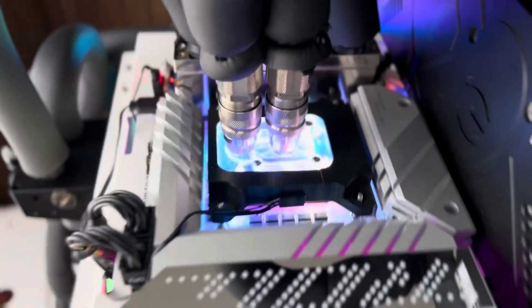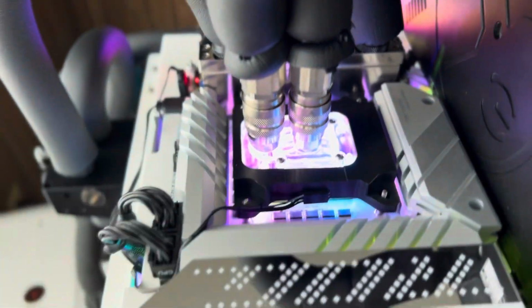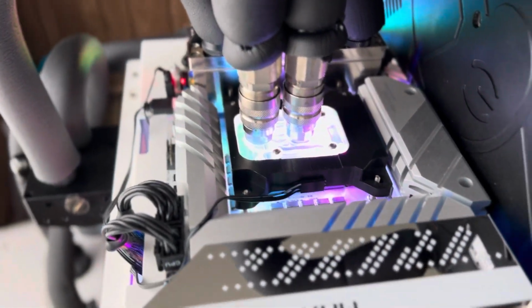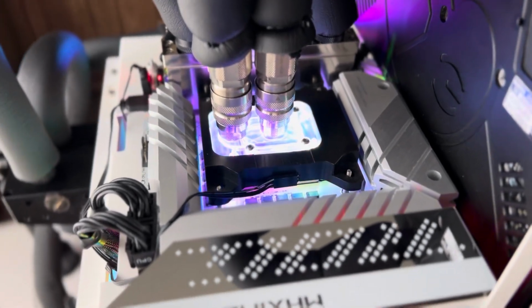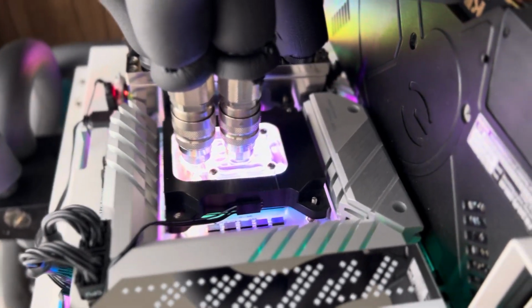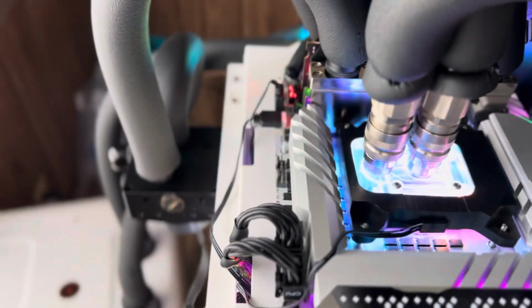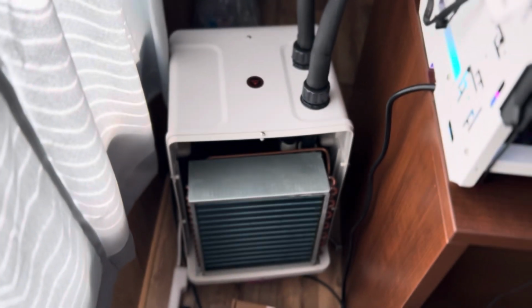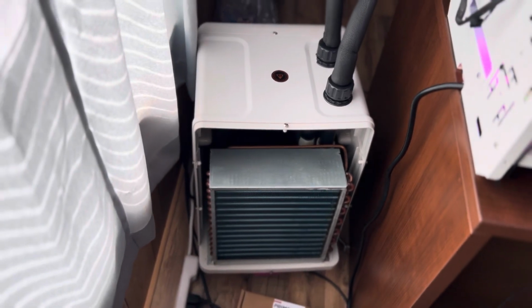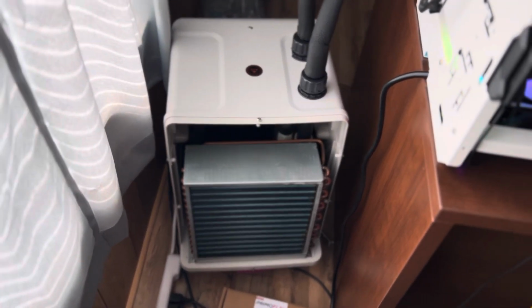However, then you have to deal with condensation, because you're setting a temperature too cold for the chiller. It's going to go below the dew point, and you'll essentially develop moisture on your system. So it's always been kind of a mild issue for me with a water chiller. That's why I got a buffer tank.